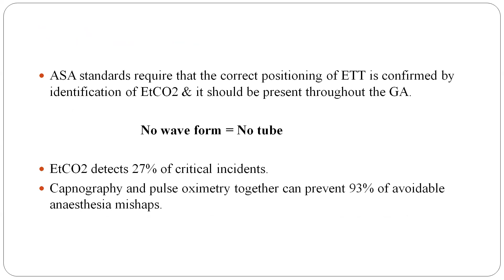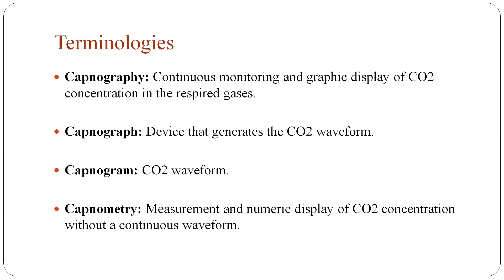Terminologies. Capnography means continuous monitoring and graphic display of carbon dioxide concentration in the respired gases. Capnograph is the device that generates the carbon dioxide waveform, and capnogram means the CO2 waveform itself. Capnometry means the measurement and numeric display of carbon dioxide concentration without a continuous waveform.